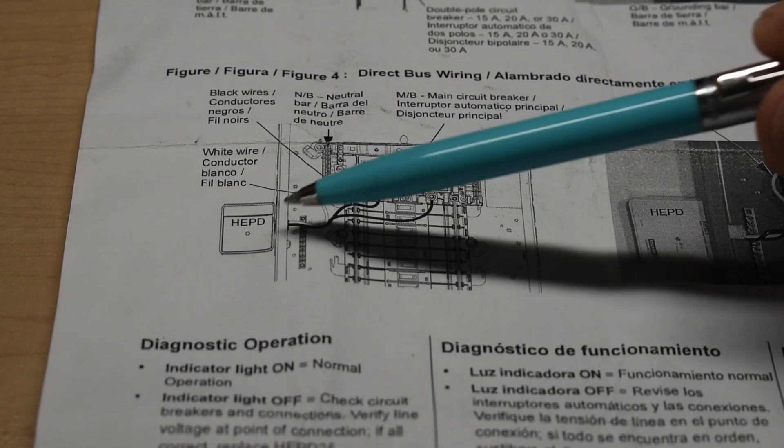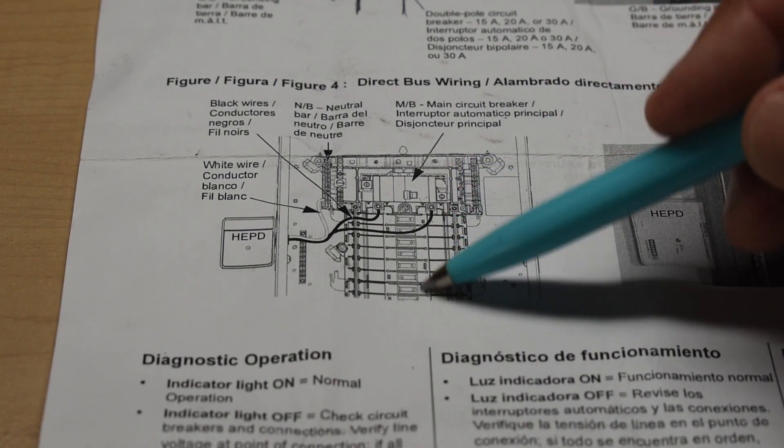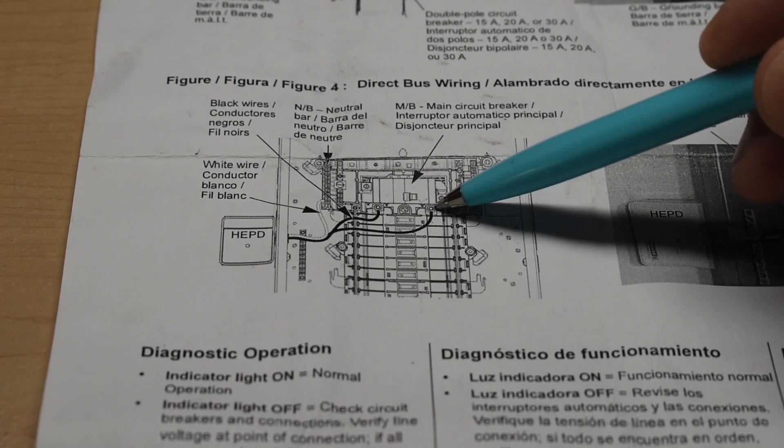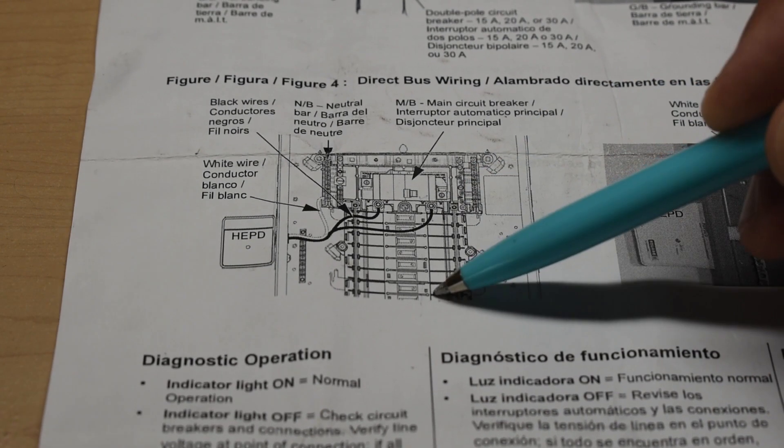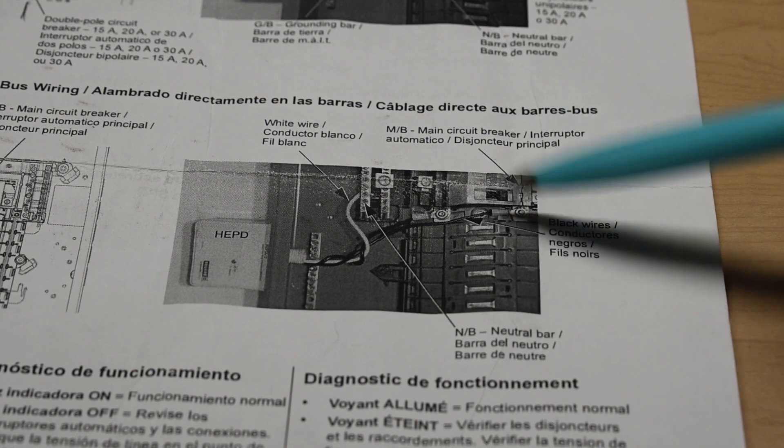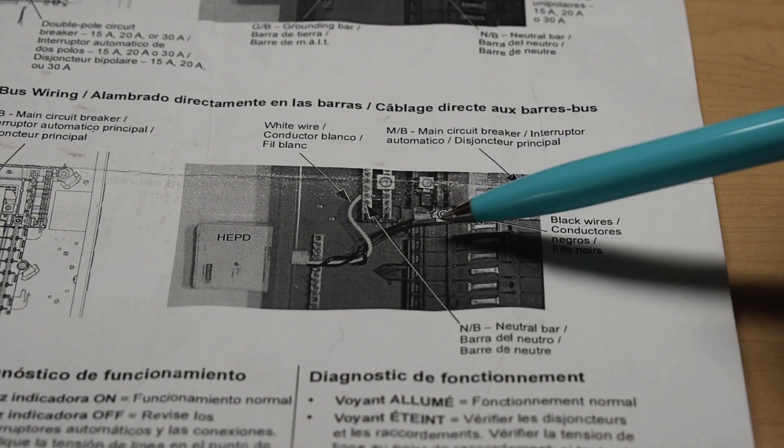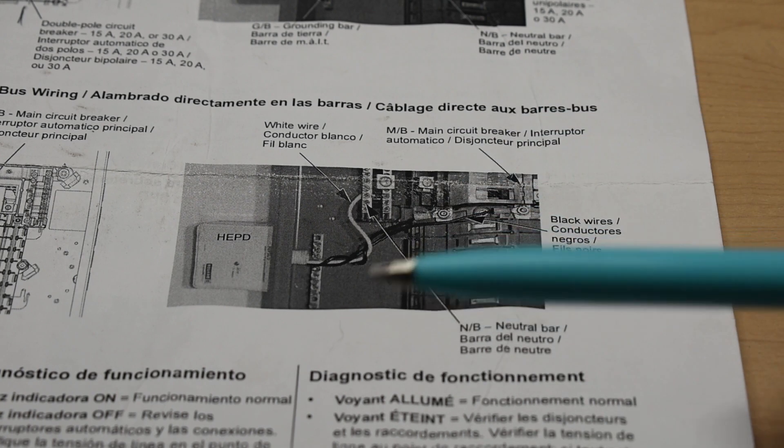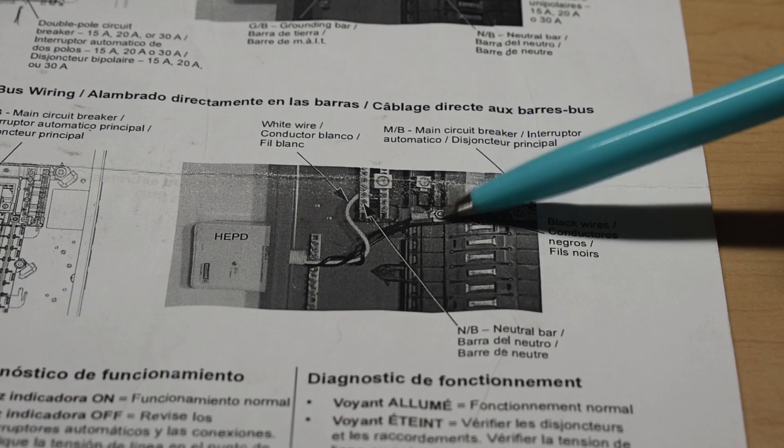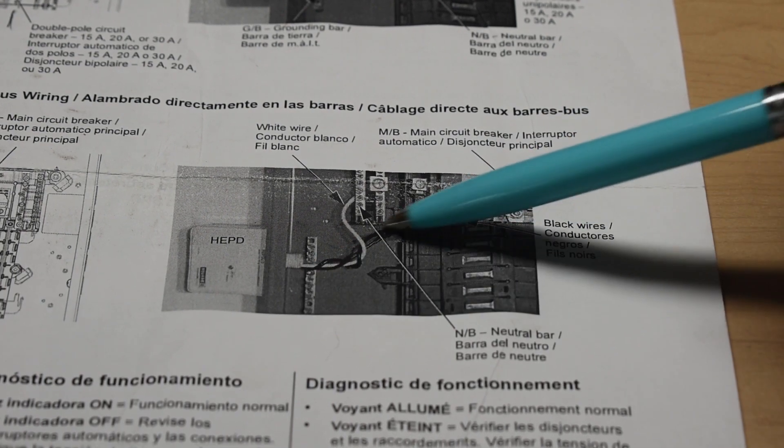If you choose not to use a circuit breaker, it's designed to also be directly connected to those bus bars, the ones that I showed you a minute ago that go all the way through behind the breakers, two bars. So you would turn off the main breaker and you would remove the nut that goes on top of the bolt that secures the breaker to the bus bar. You can see it better over here. There's one there. That's one bus bar. And over here is another. You would remove that nut. And on the end of the wire, you would have to crimp on a ring connector or a terminal end, like you see right over here. Place it over the bolt, put the nut back on and tighten down securely. Do one at a time. Remember, keep the wires as short as possible. Do not allow these routed wires to be really up against any other wires. Take the white wire, go to the neutral bar.